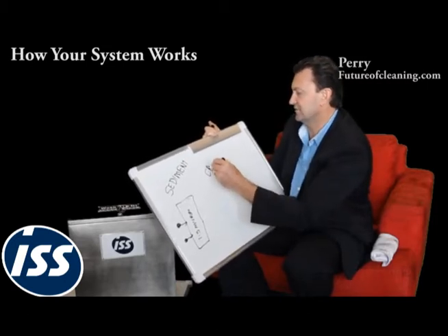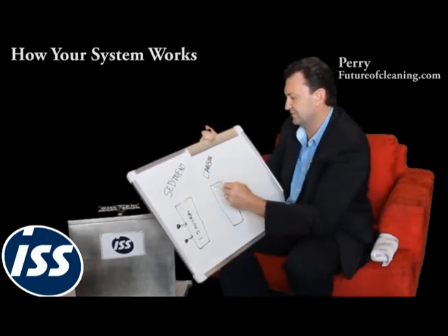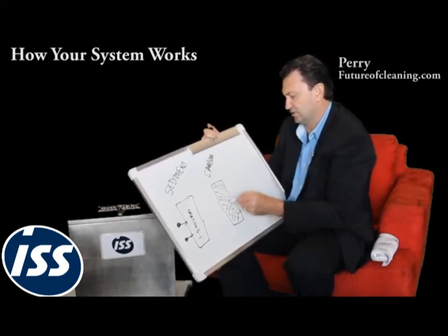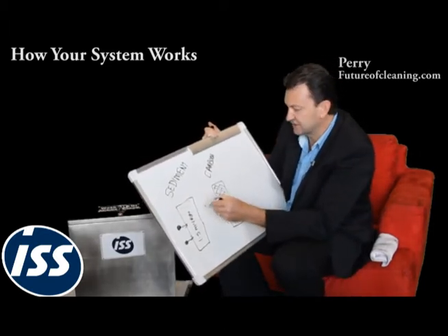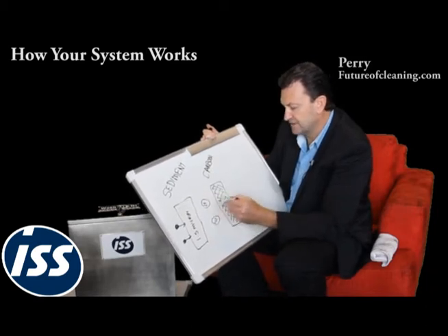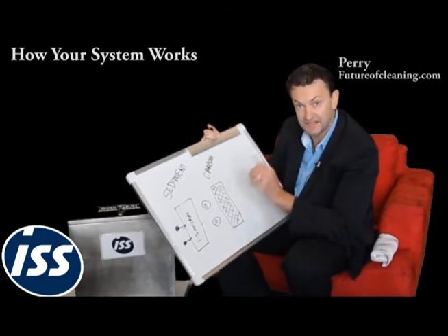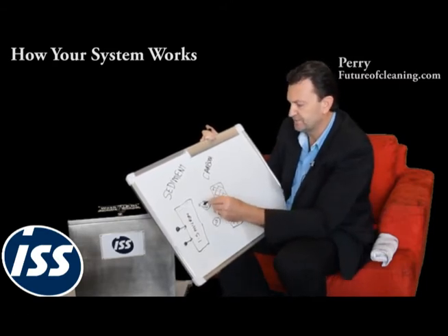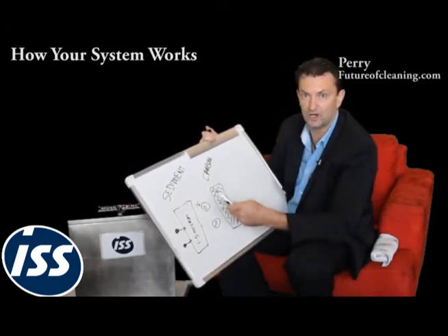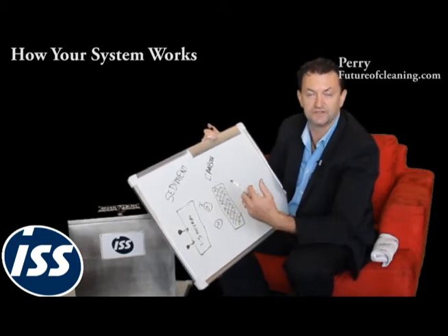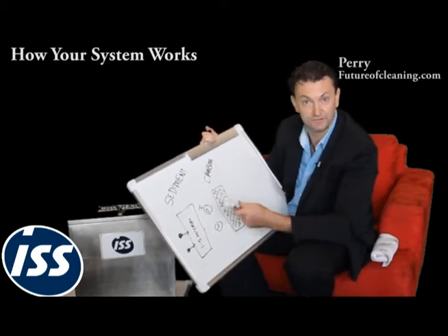The second filter that we've got is called a carbon filter. If you compare it, the carbon filter's kind of got a netting around the outside, so I'll just draw it like that. You'll know the difference when you see them later. The carbon filter's job is to take out chlorine. The reason we want to take out chlorine is that it will destroy the DI resins. It attacks the integrity of the resins, and the chlorine, as a gas, can take away a whole lot of the deionizing power of the resins. So you must have a carbon filter in before a DI resin filter.